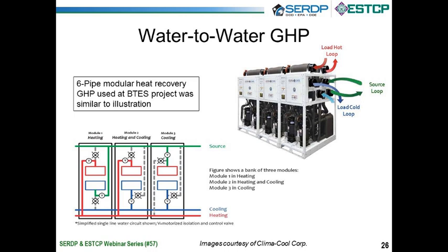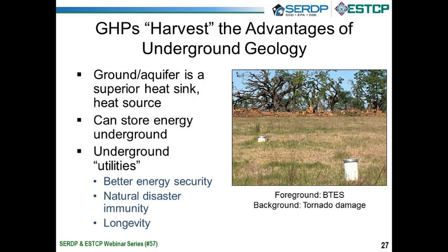We had chill water at the bottom that connected the source loop. The green goes to the BTES. As you'll see in that illustration on the left, it is a heat recovery, so we can be heating, cooling, or simultaneous heating, cooling, and getting free heat.